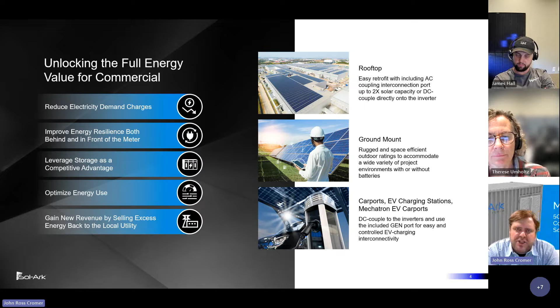the capability of powering the building plus a 500 kilowatt EV charger. And so what you can do with the Sol-ark hybrid inverters, you can plug the solar array into it through DC coupling, and you can plug the EV chargers into that GEN port. And then from the parking lot back to the building, you only have to deal with the utility conductors going out to that transformer. So you have the least number of utility conductor runs, and then you have all the infrastructure you need for high amperage EV charging and solar carports, all being managed through that Sol-ark hybrid inverter. So those are some very competitive applications of our product.